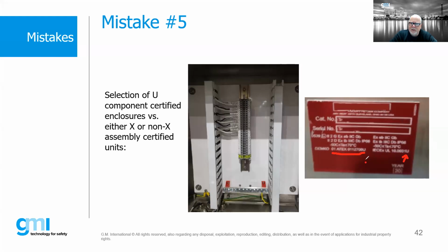Again, if you see this U, that's a problem. The other hint that you will see is that there is no T code. Why is there no T code? Because the manufacturers supplied this empty. They don't know what you're going to be putting in it. That T code could change based upon the number of terminals or the various devices that you're putting on the inside of this thing. This is one of the biggest issues that I see with so many different people that buy EX equipment, that they buy component certified products, and then they fail to understand by adding components or doing something different that this product will violate its certificate, and we cannot do that.